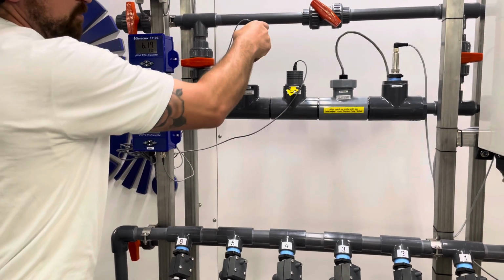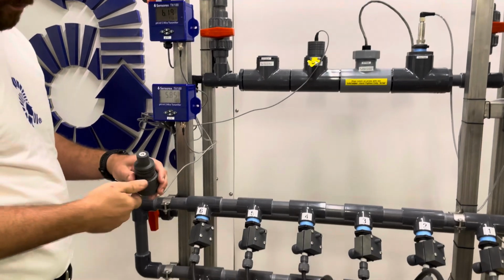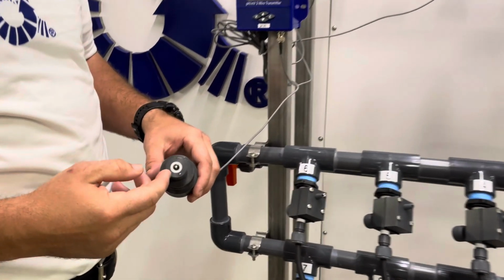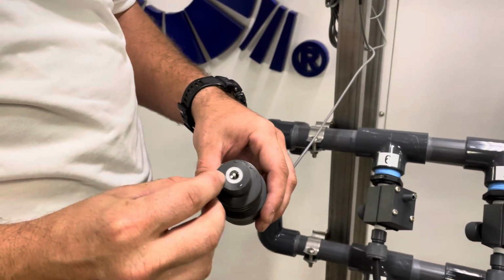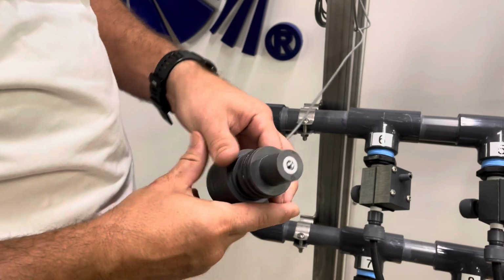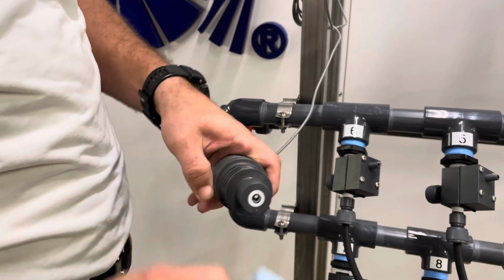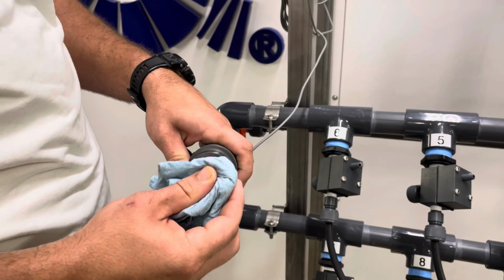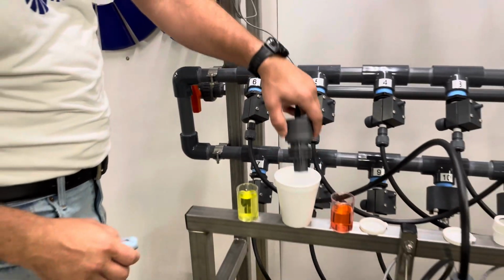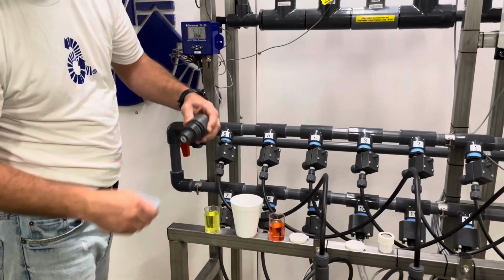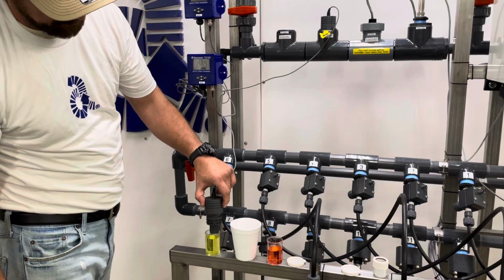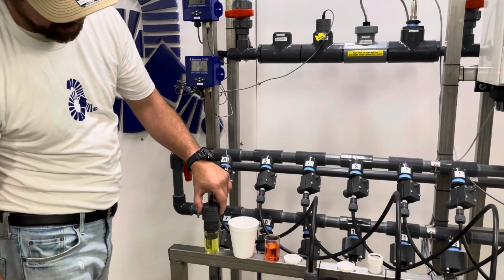We pull out our pH probe. We'll visually inspect it to see if the glass is broken and if there's an air bubble. And after doing that, we'll clean it. We'll rinse it in water. And then we're going to put it in the 7 solution. We shake it around so there's no air bubbles.